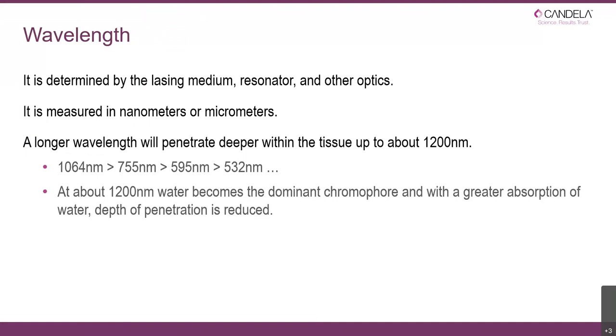The parameters we're using are the wavelength, the pulse duration, the fluence or energy being delivered, and the spot size — how quickly we can cover a specific area or treat very small areas. The wavelength is determined by the lasing medium and measured in nanometers or micrometers. The longer the wavelength, the deeper it will penetrate into the tissue — up to around 1200 nanometers, at which point water starts to become the chromophore.